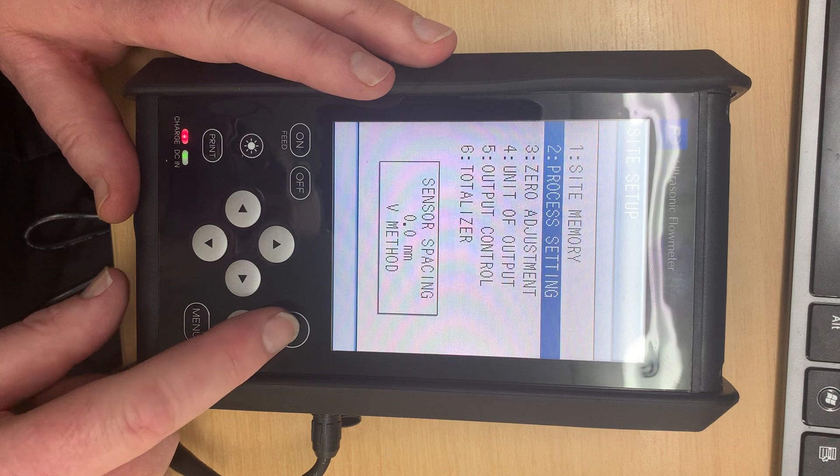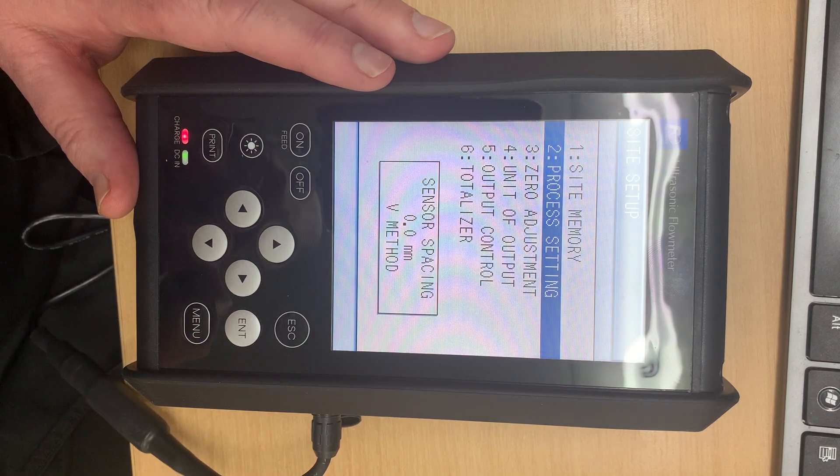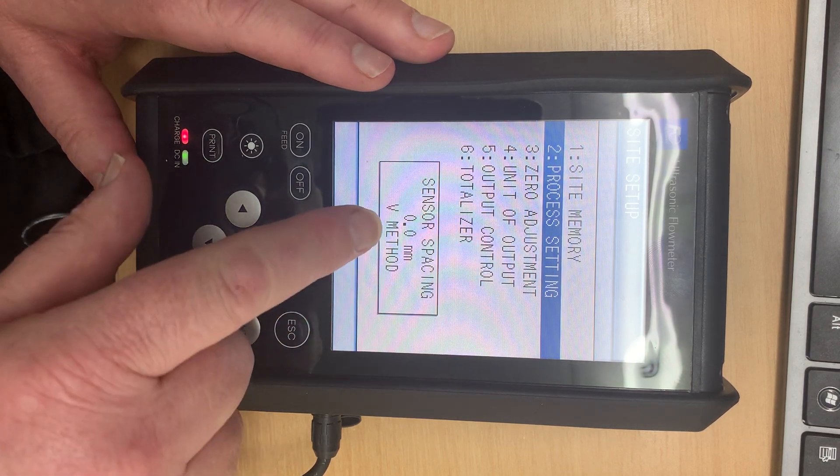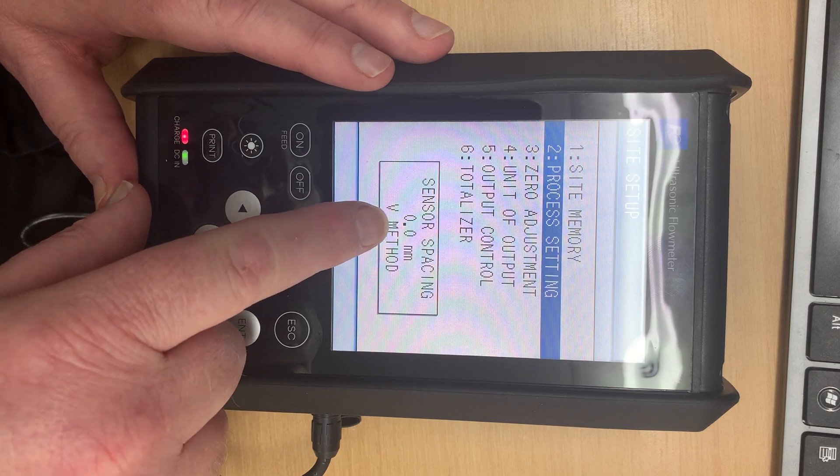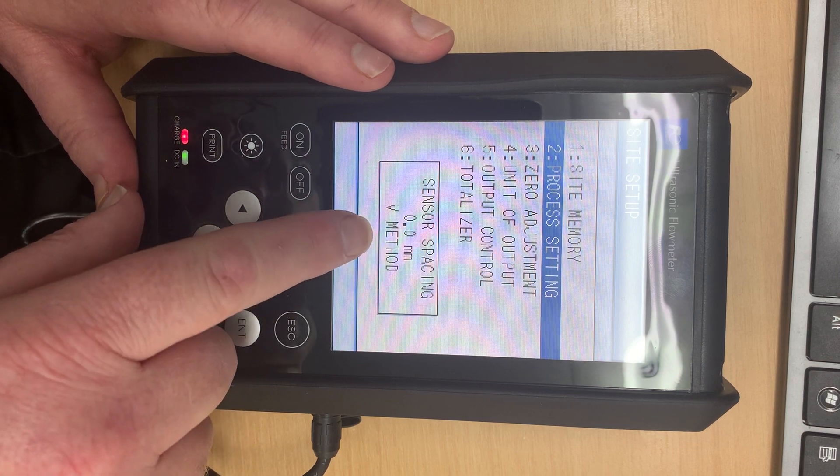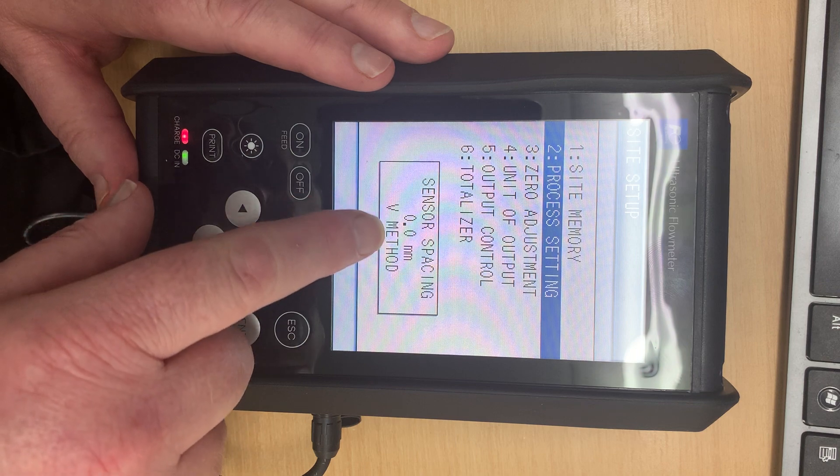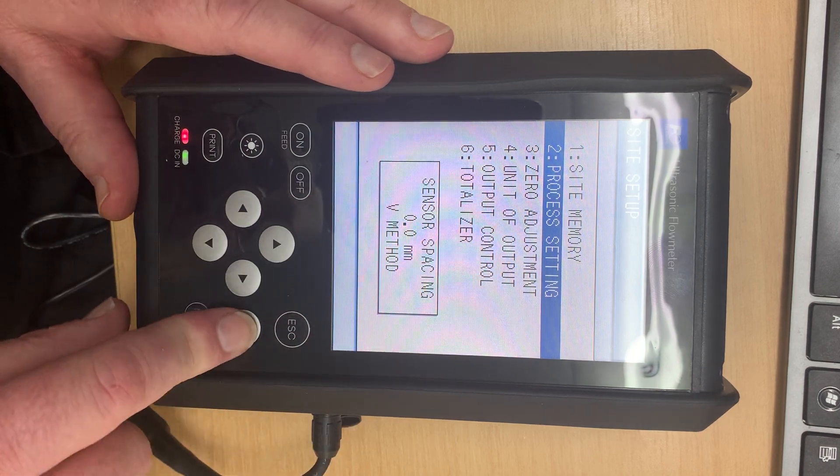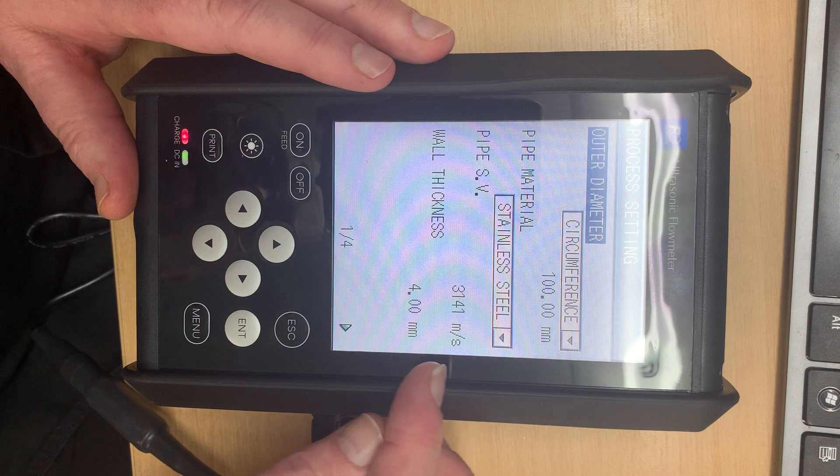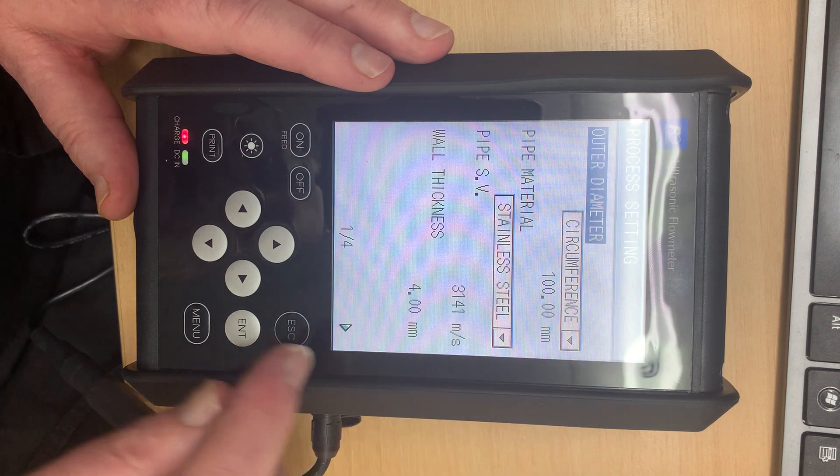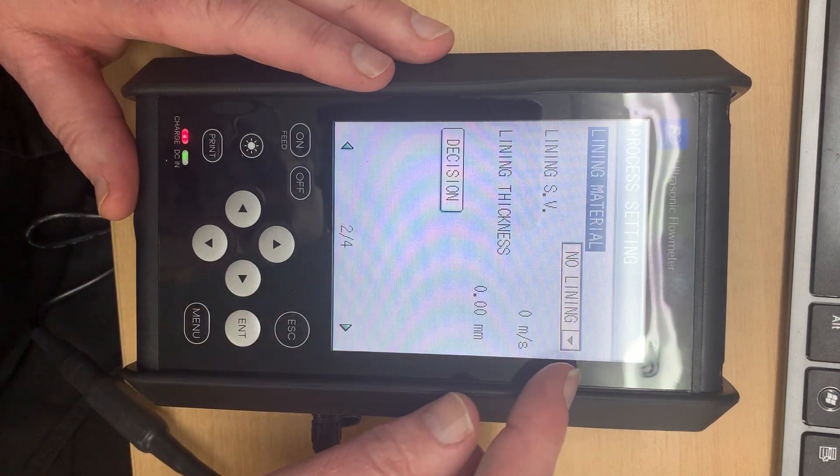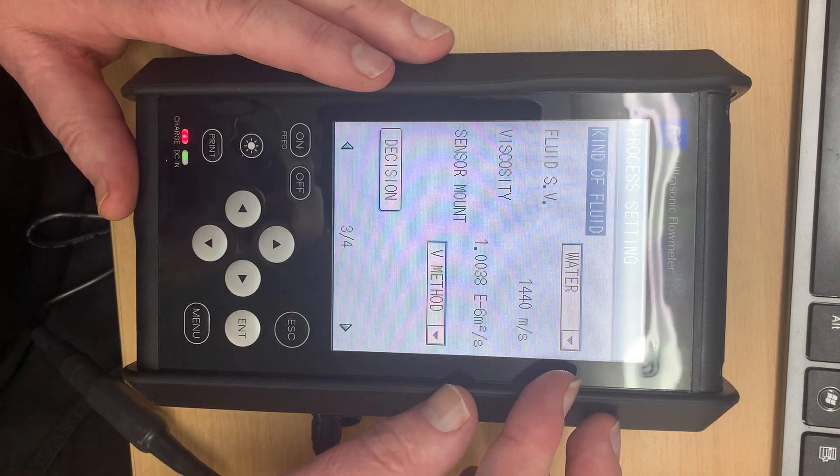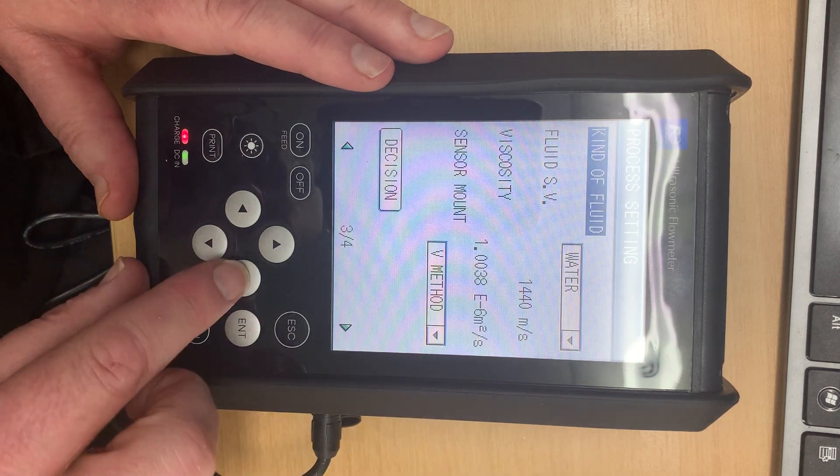Now we hit escape and we go back to the process settings. Now I've put something wrong because normally it would come up here and say sensor spacing for this setup should be X. And in this case it said that it's 0.0. So obviously I've done something wrong in my setup. We have wall thickness. We have circumference. We have no lining. We have water. We have V method.